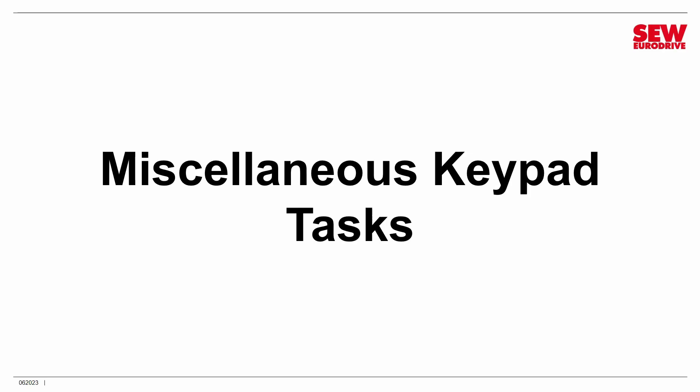All right, now we have already used the DBG60 keypad once. I've shown you how to do a number of things, but now that we're in expert mode, there are a few additional things that I'd like to show you. I'm going to show you how to change parameters using the keypad. It's a slightly arduous task with the keypad, but it can be done, and if that's all you have, sometimes it's what you have to use. I'm also going to show you how to use the keypad to make backups of the parameter set. You can use this feature if you want to create a bunch of identical Movimots. What you would do is parameterize one, then make a backup with the keypad, and then just go down the line and restore the keypad backup onto each additional Movimot.